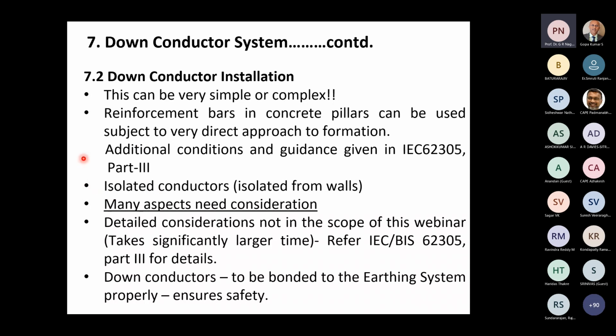And then the other possibility is that reinforcement bars inside the concrete pillars can be used as down conductors, subject to a very direct approach. You see, this does not necessarily mean a straight line approach. A direct approach means the reinforcement bars must have metallic continuity.